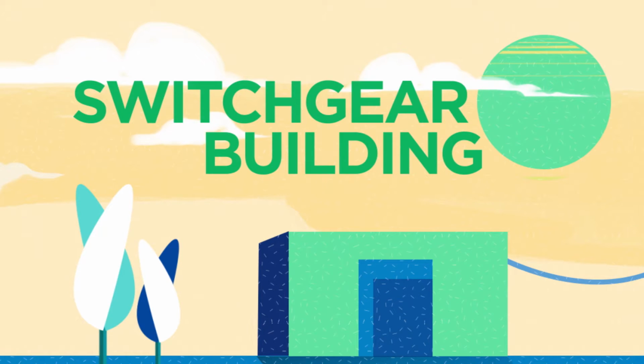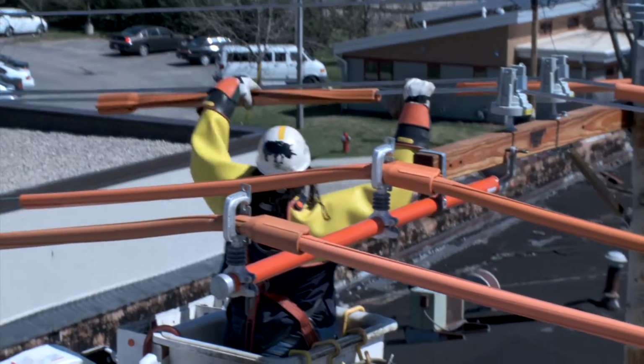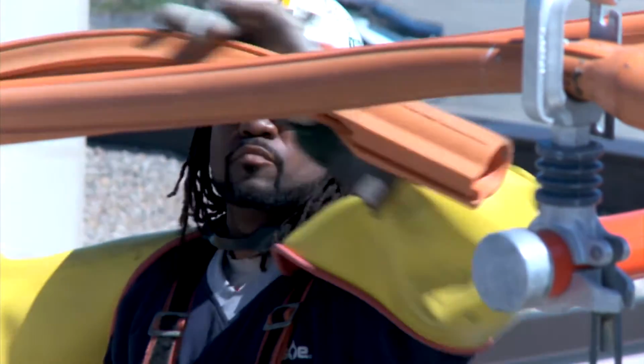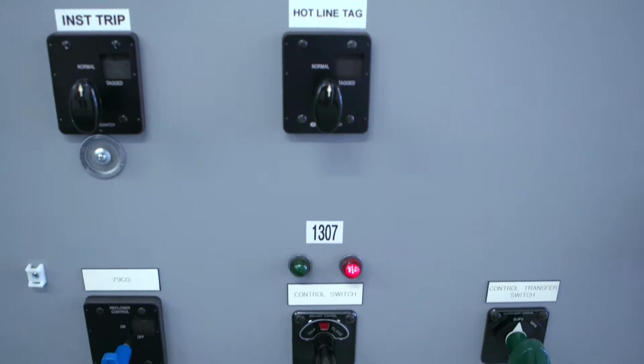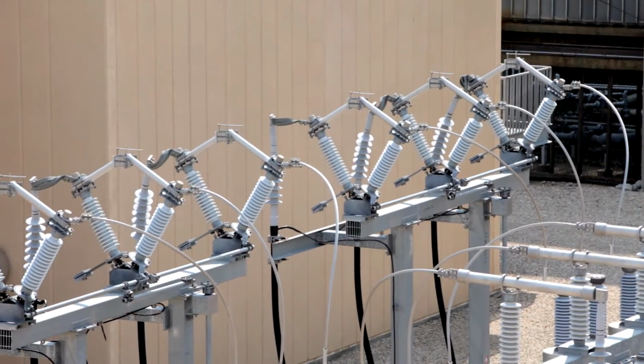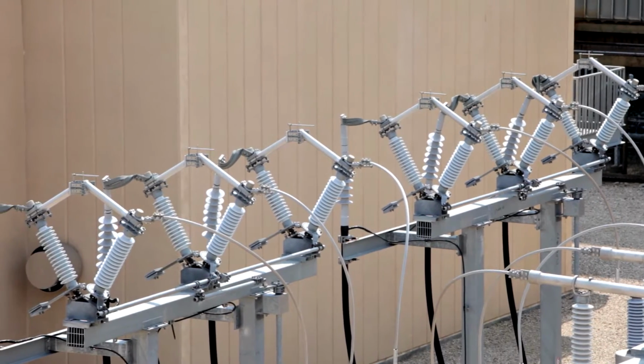to our operations center. Our operations center has complete oversight, control, and monitoring of all of our equipment that is located in the substation. Therefore, if we have a problem, an alarm, we have a piece of equipment fail, wildlife gets in the substation, trips it out, they have immediate response time as far as knowing what exactly is going on, the appropriate personnel to dispatch, so that we can get a timely response. The purpose of switchgear in the substation is to take the power from the substation and distribute it to the distribution feeders that are served out of the substation.